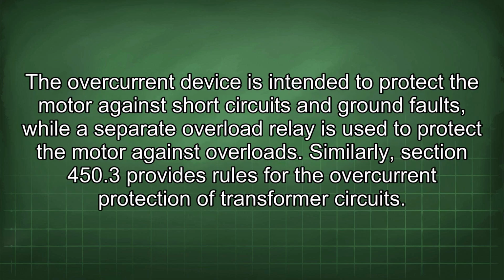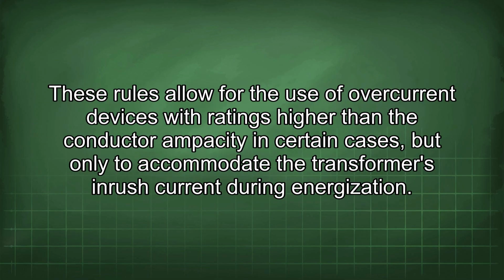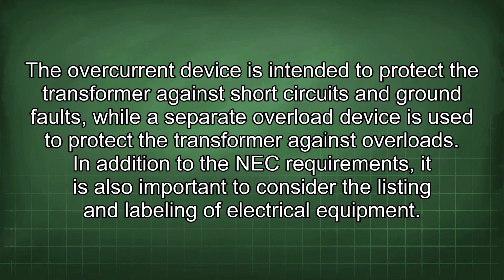The overcurrent device is intended to protect the motor against short circuits and ground faults, while a separate overload relay is used to protect the motor against overloads. Similarly, Section 450.3 provides rules for the overcurrent protection of transformer circuits. These rules allow for the use of overcurrent devices with ratings higher than the conductor ampacity in certain cases, but only to accommodate the transformer's inrush current during energization. The overcurrent device is intended to protect the transformer against short circuits and ground faults, while a separate overload device is used to protect the transformer against overloads.